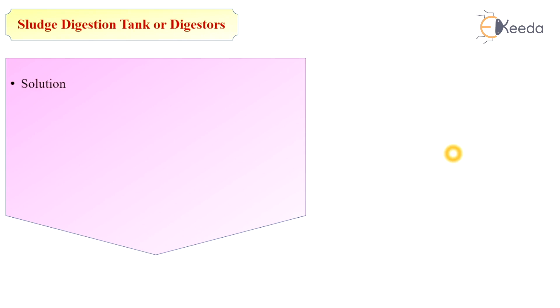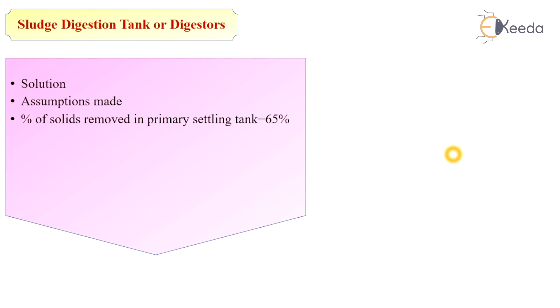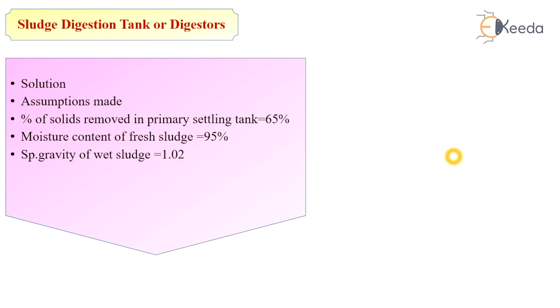Before starting the actual design, we make the following assumptions: percentage of solids removed in the primary settling tank is assumed as 65%; moisture content of fresh sludge is 95%; specific gravity of wet sludge is 1.02; digestion period is 30 days; depth of the digestion tank is 6 meters. These are the assumptions made while designing the digestion tank.